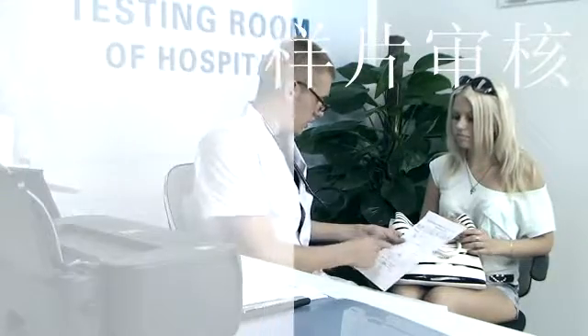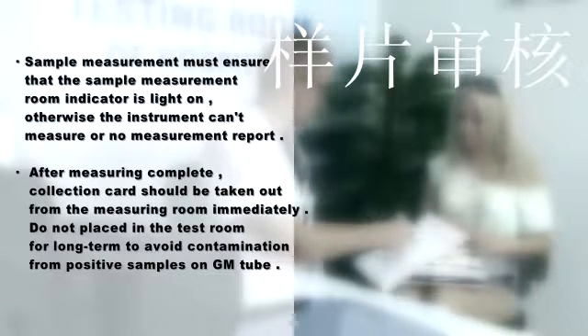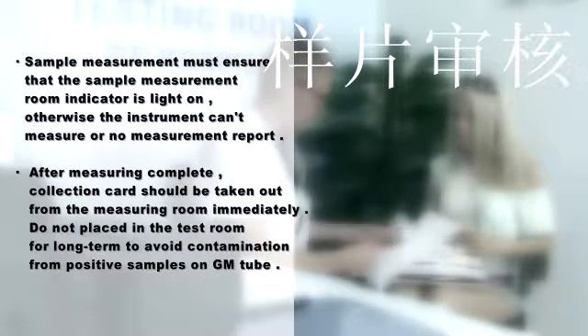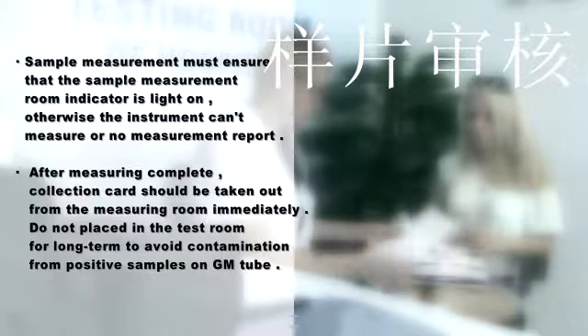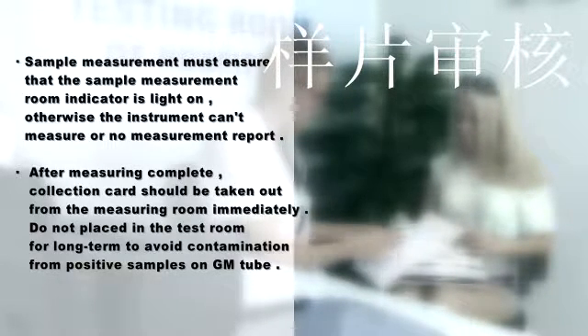The screen will then display the results. Sample measurement must ensure that the sample measurement room indicator light is on; otherwise, the instrument cannot measure or no measurement report will be generated. After measurement is complete, the collection card should be taken out from the measuring room immediately. Do not place it in the test room long-term to avoid contamination from positive samples on GM tube.